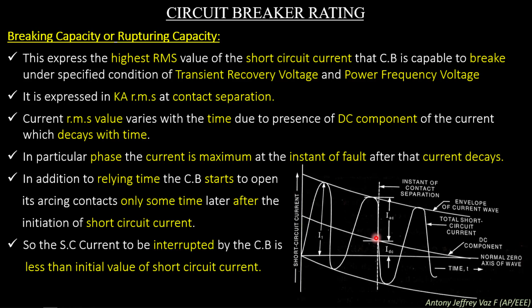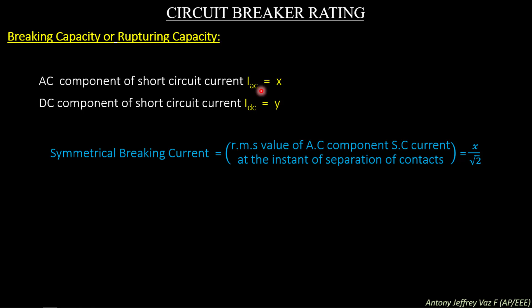Breaking capacity or rupturing capacity can be expressed with a formula. AC component of short circuit current, IAC, equals X. DC component of short circuit current, IDC, equals Y. Symmetrical breaking current equals the RMS value of the AC component of short circuit current at the instant of separation of contacts, which is X divided by root 2. Because we are taking the RMS value, we are dividing by root 2. Here X is the AC component, so to get the RMS value of the AC component, we need to divide it by root 2.